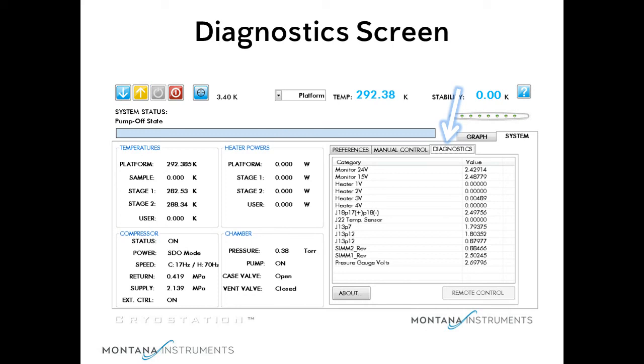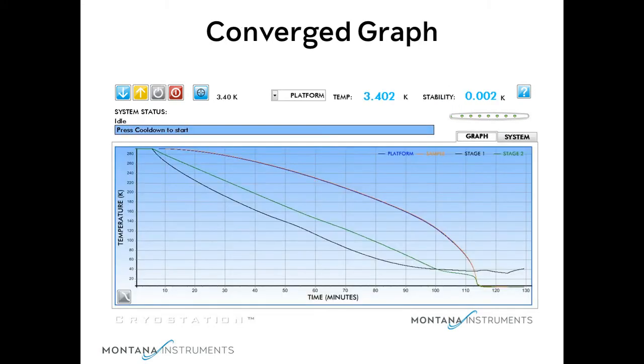We'll come back in a little bit after the system has had a chance to cool down. As you can see from the graph, we've reached our target temperature, and the graph shows small variations. From the looks of this graph, we have achieved a stability of about 2 mK.